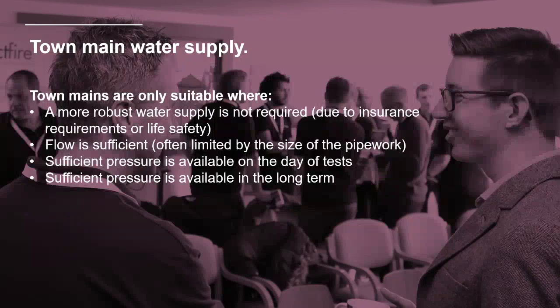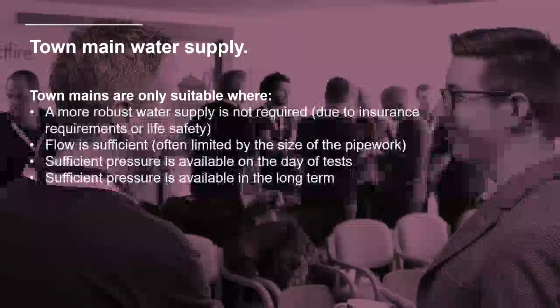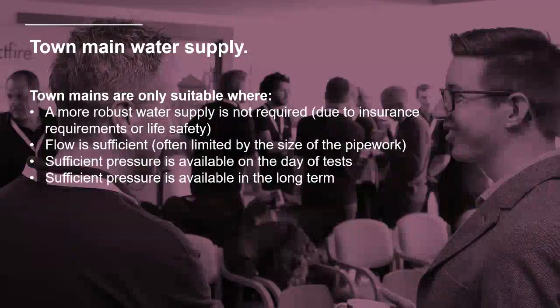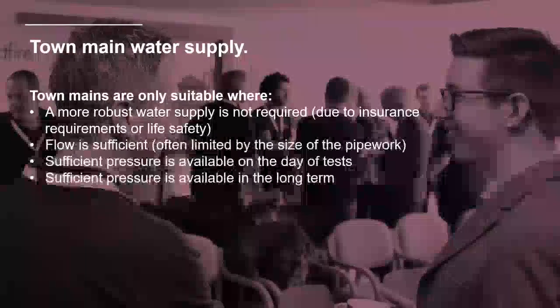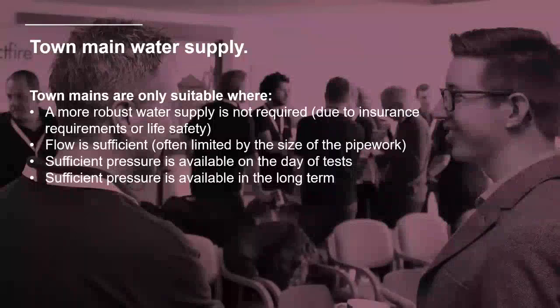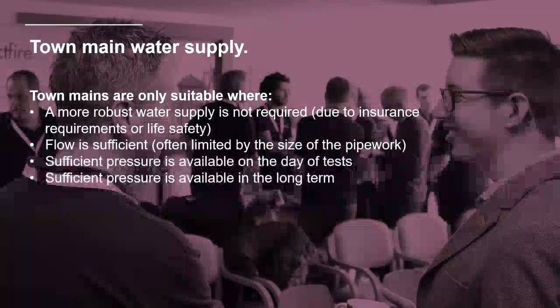Town main is only suitable where there is sufficient flow, as we've already mentioned, and where there is sufficient pressure available on the day of the test. So we need to prove that pressure is available, and also that it's available in the long term. Now that is quite tricky.